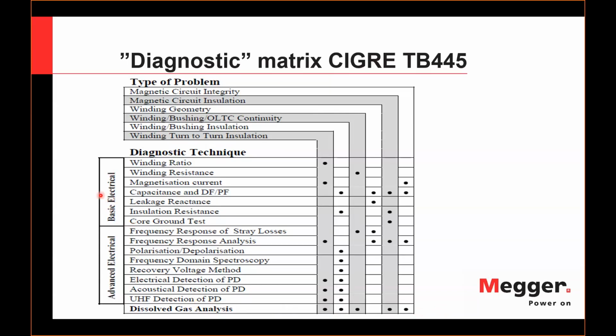The tests can be grouped under basic or advanced tests. Within basics, you're simply rechecking the design and geometry parameters that are set by the manufacturer, by the designer. And you always have a comparison: what was before, what was in the commissioning phase. You can always open those reports and compare. In the advanced testing, you are looking at all types of frequency responses, like Ken and Diego mentioned previously. The transformer usually does not see those frequencies, but they are very useful to see material worsening or geometrical change in the structure of the transformer at a very early stage, before the problem becomes very critical.